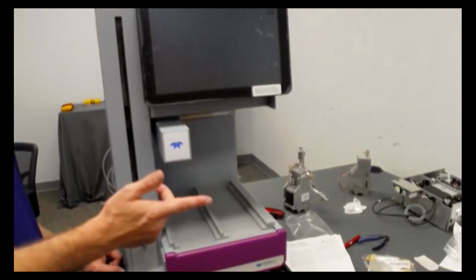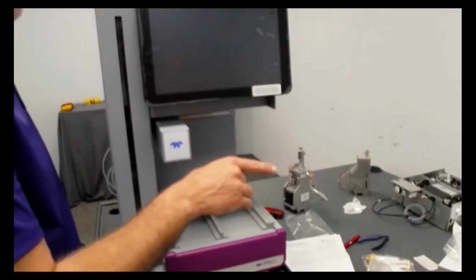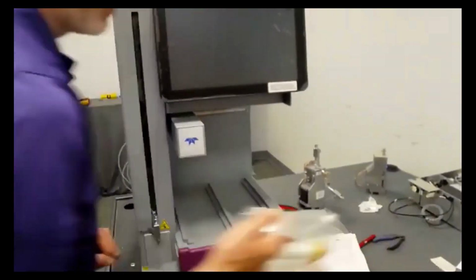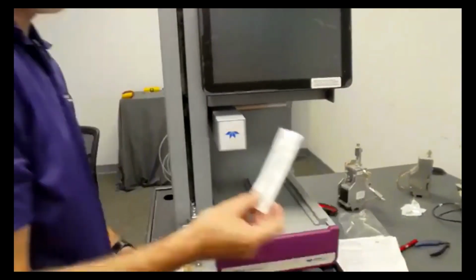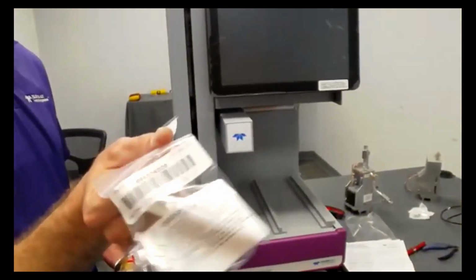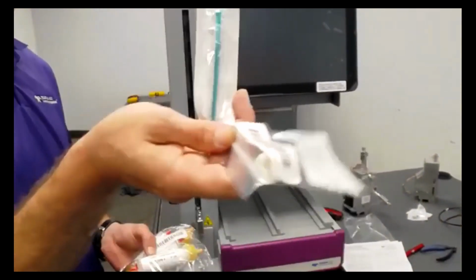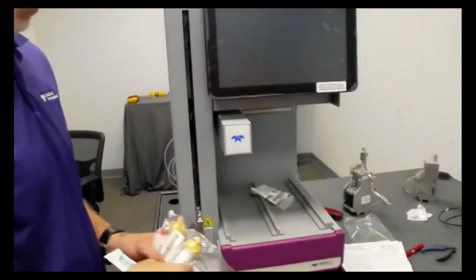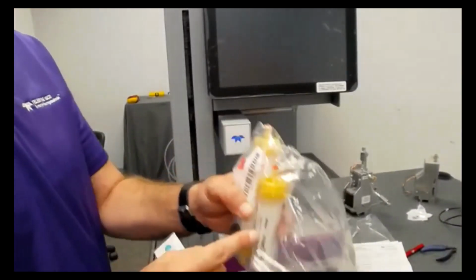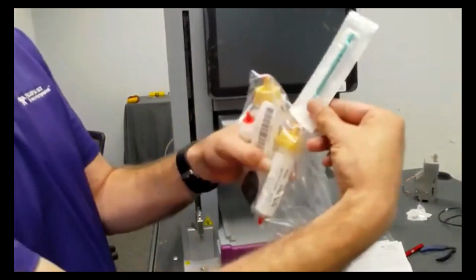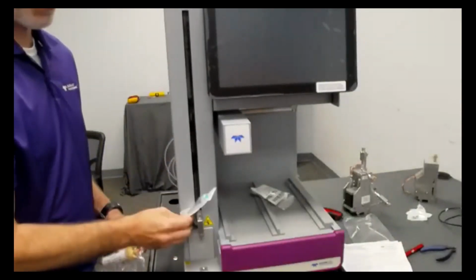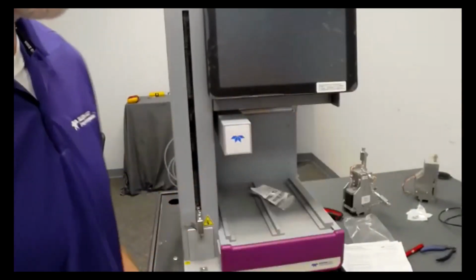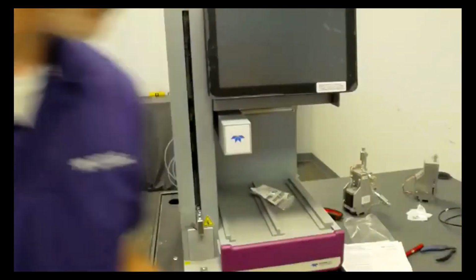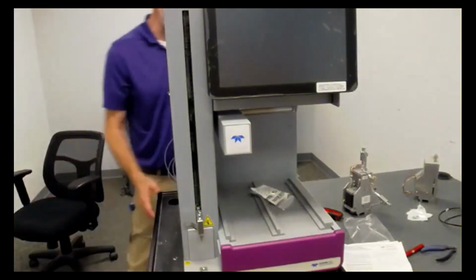And you want to pick resolution, and all of this is in the instructions. And when it's done equilibrating, what you'll do is you'll take 1 mL of the sample that you prepared in here. You'll take 1 mL of it in your green syringe. And when you're done equilibrating, you just load it on the top of the column. Just load it right there on the top of the column, put it back down, press play. Universal test mix will take about 15 minutes to run.